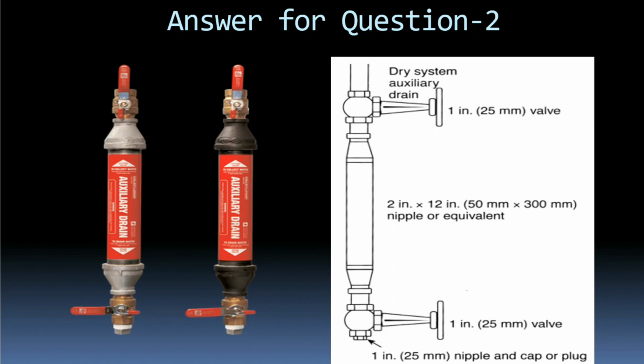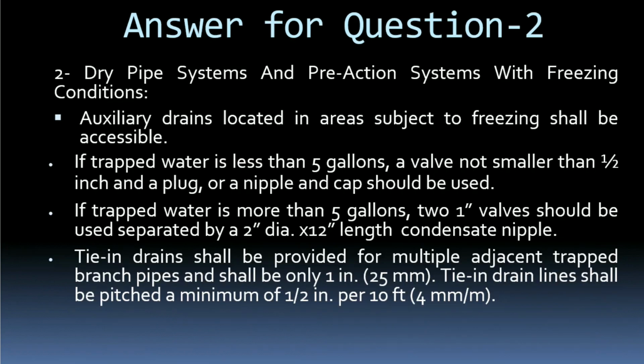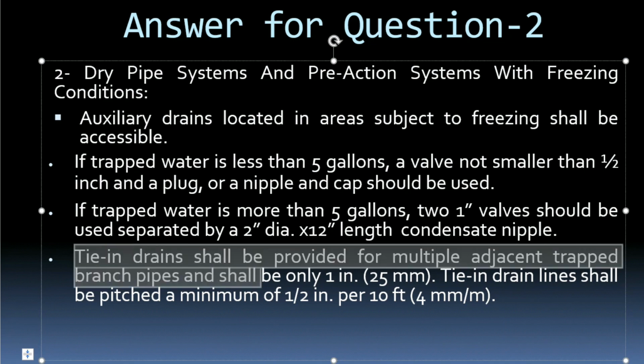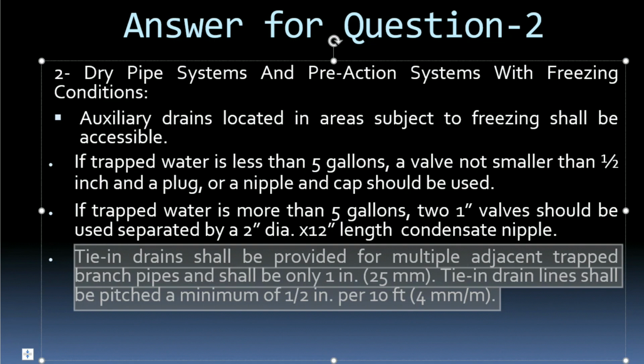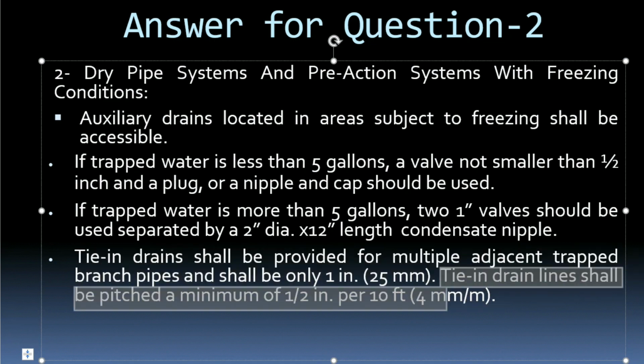First of all, the top side here has one valve and here one valve. So we have to propose this type of arrangement. And second, if you have multiple arrangements like this, tie-in drains shall be provided for multiple adjacent trapped branch pipes. That should be 1 inch. And the tie-in drains shall be pitched, that means the slope. So for 1 meter there should be 4 mm slope. First of all, if you have multiple arrangements, you have to connect all these drain lines with a 25 mm line. Second thing, you have to provide 4 mm slope per meter.